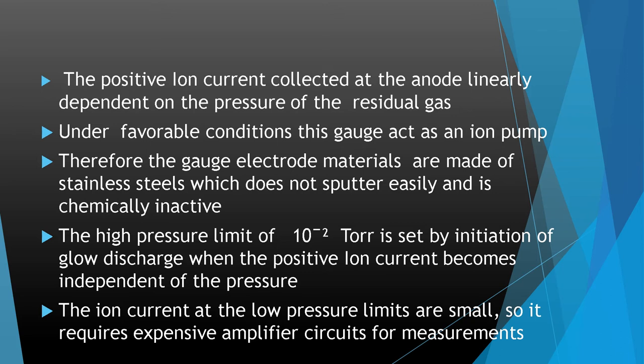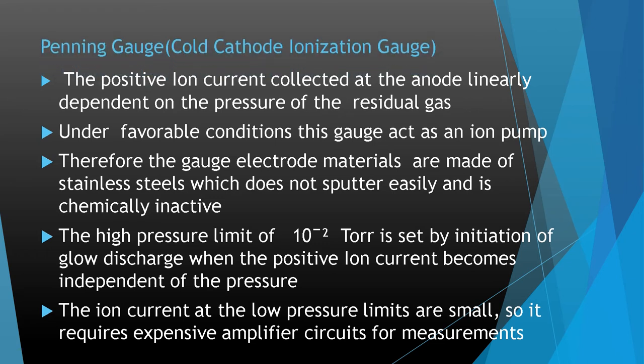Under favorable conditions, this gauge can act as an ion pump. Therefore, the gauge electrode materials are made of stainless steel, which does not sputter easily and is comparatively chemically inactive. The high pressure limit of 10⁻² Torr is set by the initiation of glow discharge, when the positive ion current becomes independent of pressure. At the low pressure limit, the ion currents are small, so expensive amplifier circuits are required for measurement.